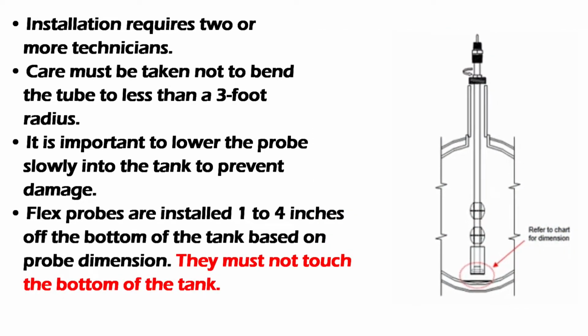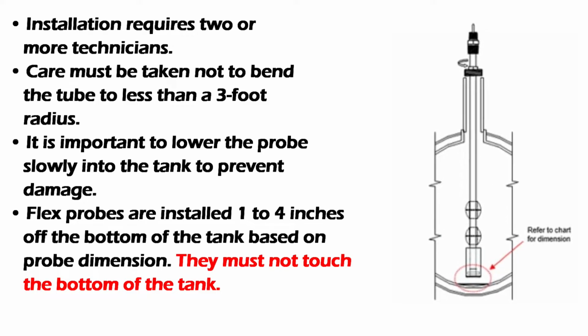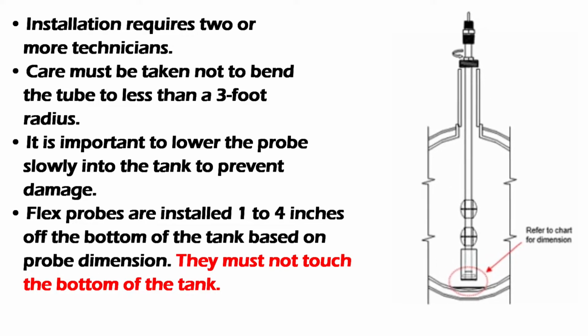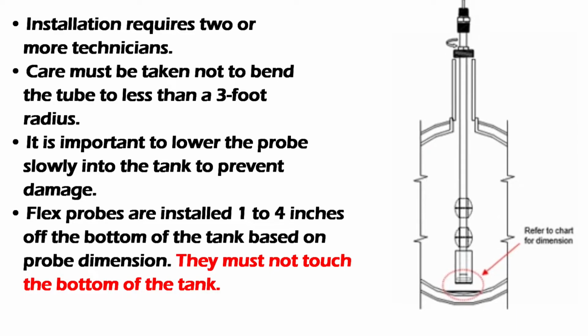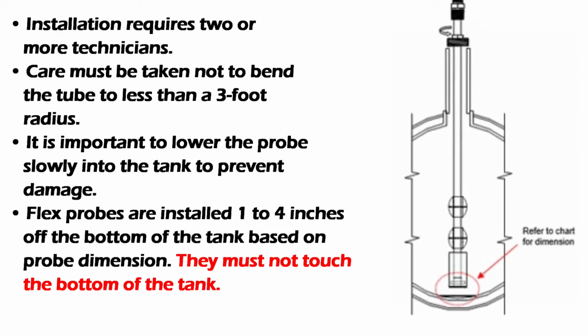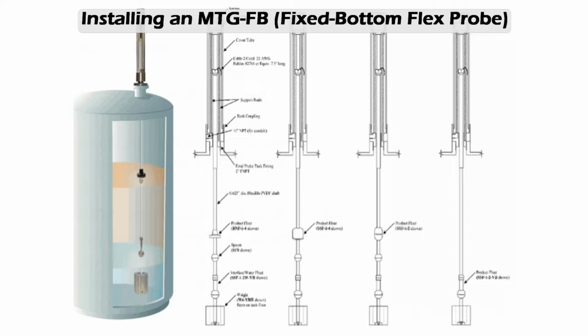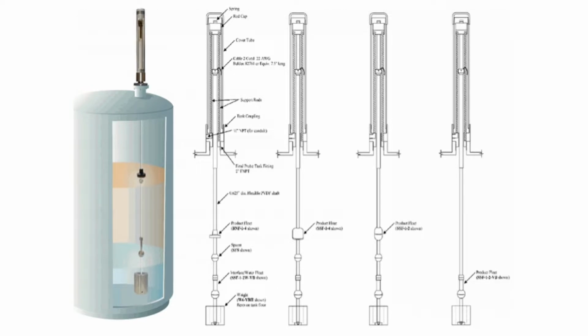Top mount flex probes are installed 1 to 4 inches off the bottom of the tank based on probe dimensions. They must not touch the bottom of the tank. Installing an MTG-FB fixed bottom flex probe. As with the top mount flex probe, the installation of a fixed bottom flex probe should be done by 2 or more technicians. Care must be taken not to bend the tube to less than a 3-foot radius, and it's important to lower the probe slowly to prevent damage.